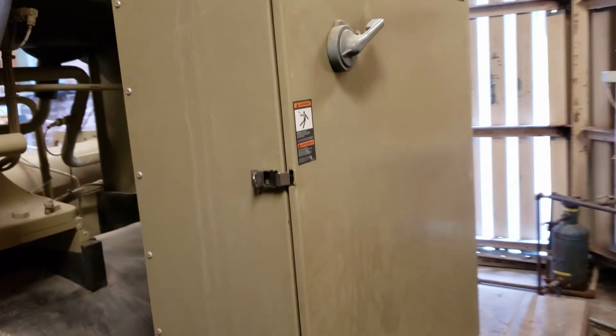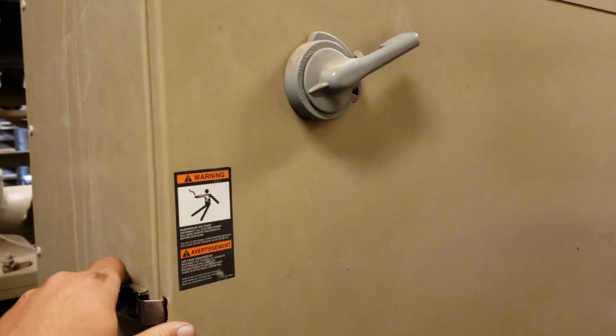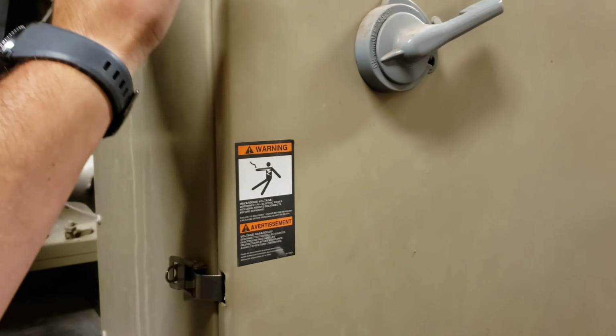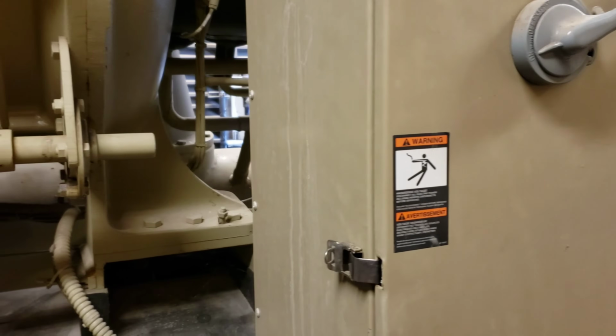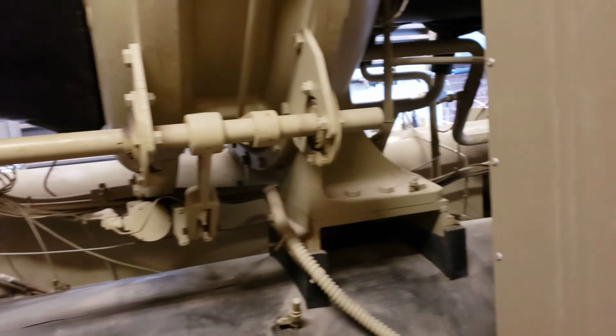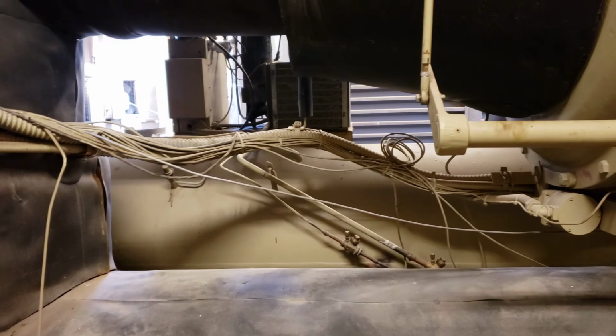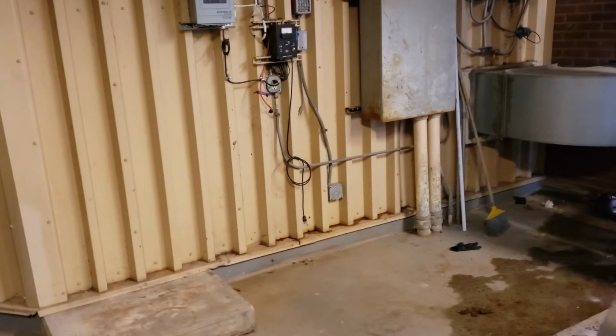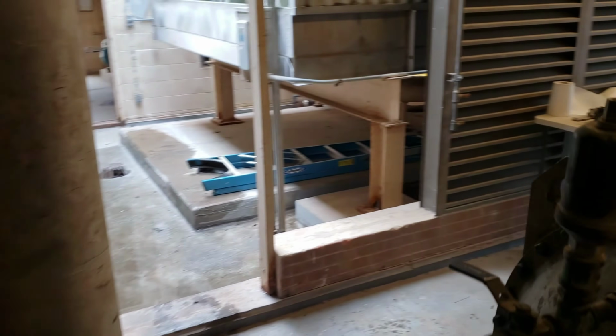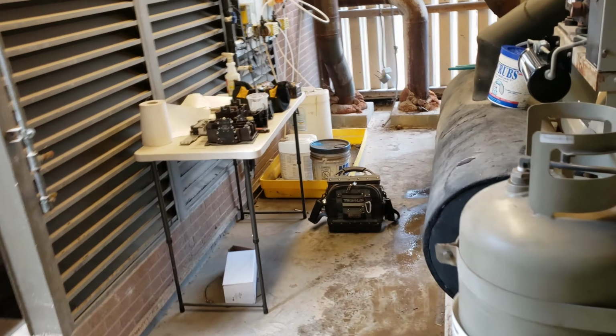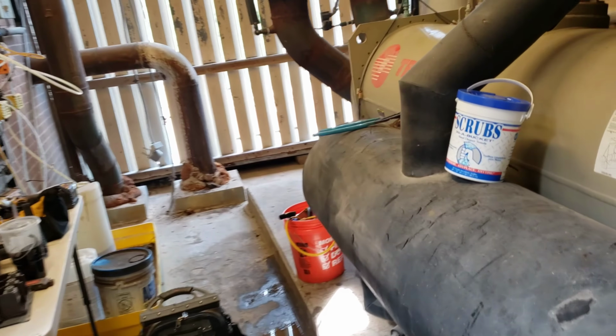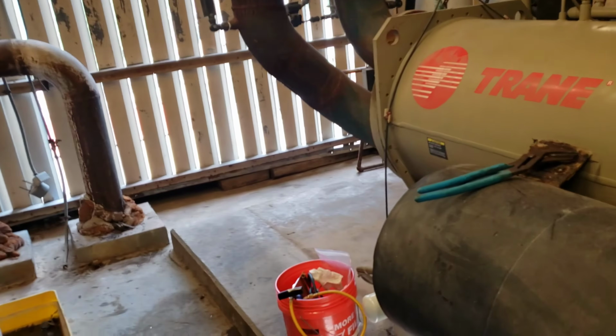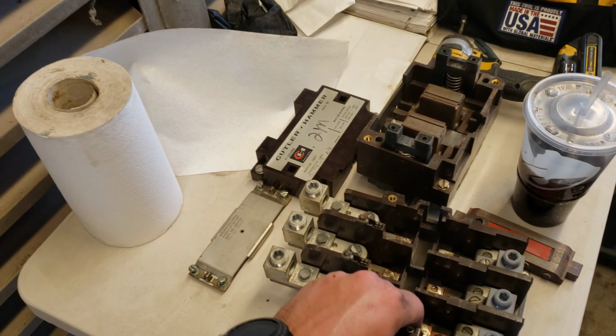But anyway, so this chiller had a starter issue on starter 1. It's a Y delta start. The coil was beginning to fail on it. It couldn't properly maintain the hold. So anyway, replaced the starter coil. That took care of that problem. Now it's working perfect. That allowed me to continue to run, because what it was doing is every time the chiller would try to turn on, the starter had a really loud buzz to it. You can see this. I used an old starter they had for parts.